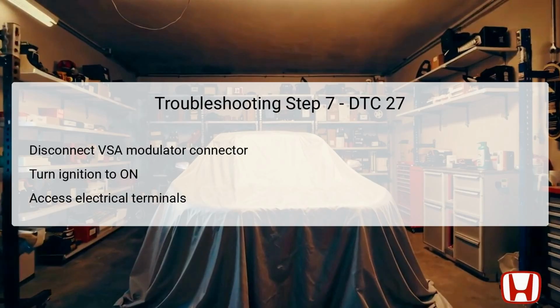Afterward, the technician will access specific terminals within the VSA modulator control unit. Terminal numbers 13 and 25 will be measured for voltage. It's essential to conduct these measurements carefully to obtain reliable data that will guide the next steps in addressing the fault.